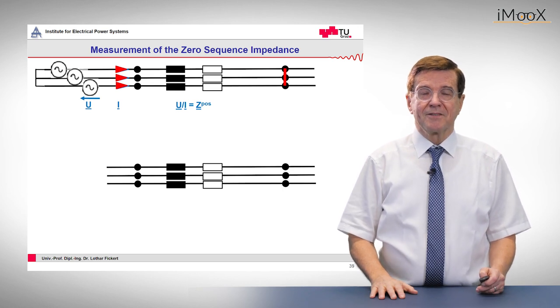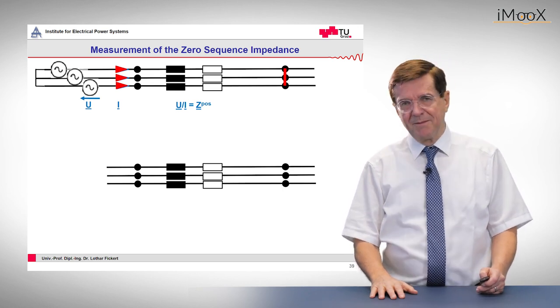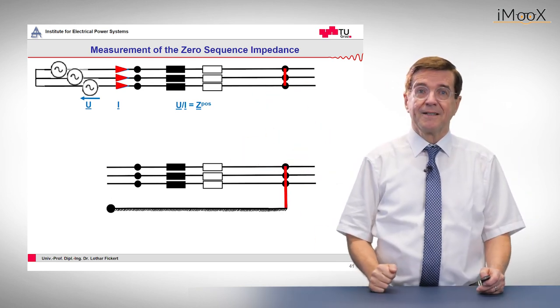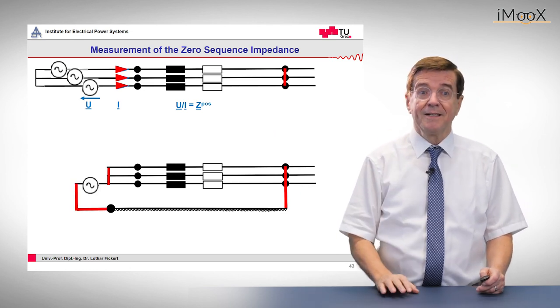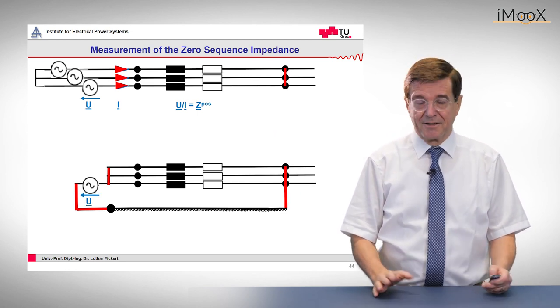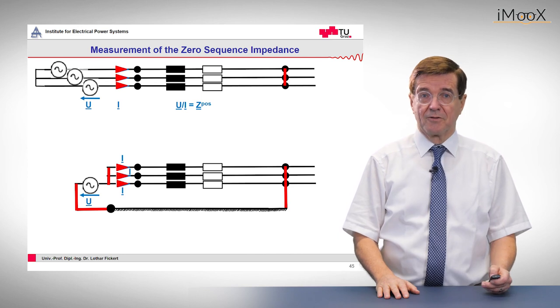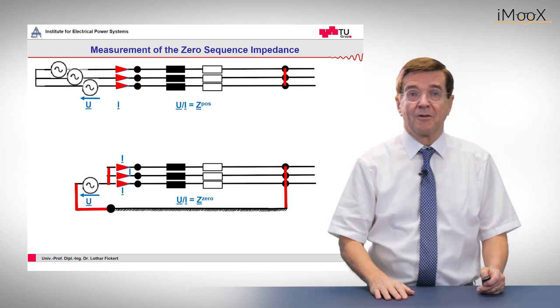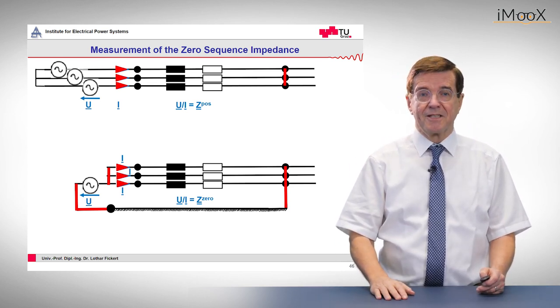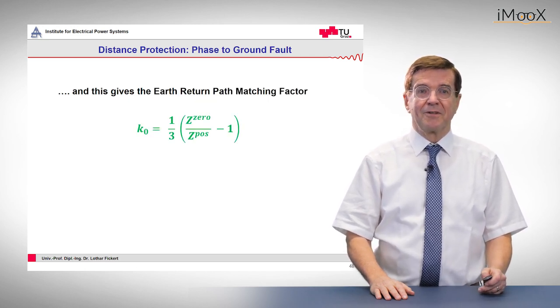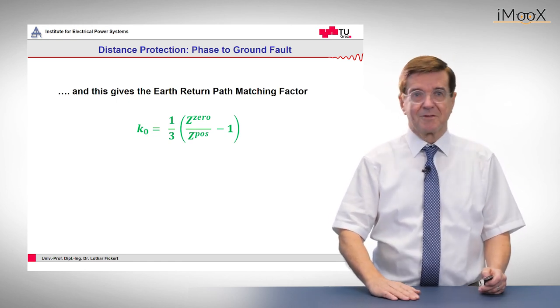The zero sequence impedance is determined in a similar way, but not the same. In this case we short-circuit the line at the end, then short-circuit the three phases together at the beginning and apply a single-phase voltage source to it. That means we generate three identical fault currents through this loop. The quotient of this voltage divided by one of these line currents is the zero sequence impedance. From this we can determine the earth return path matching factor by dividing: zero sequence minus positive sequence, divided by positive sequence, and so on.